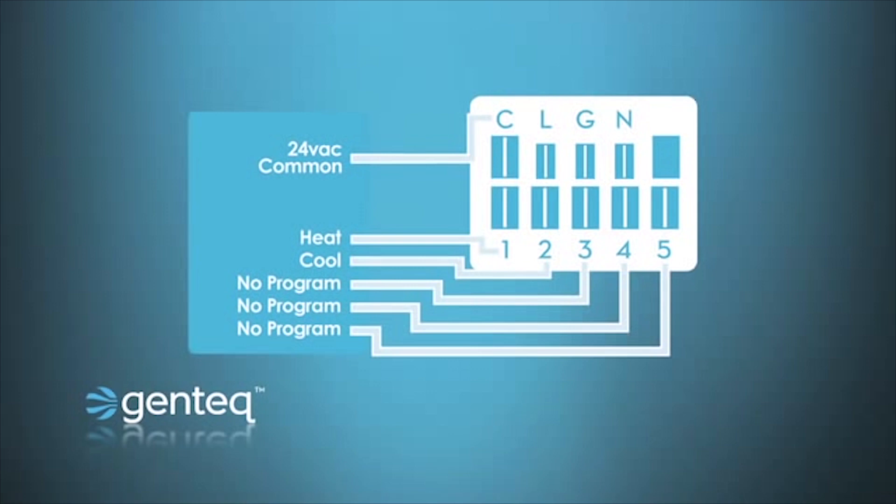However, we also notice that there's three of the taps on the motor that say no program. That's because the manufacturer does not have to program all five taps of the motor. So as I mentioned before, this connection block will always be the same. There's always the potential for five speeds or torque settings out of the X13 motor.